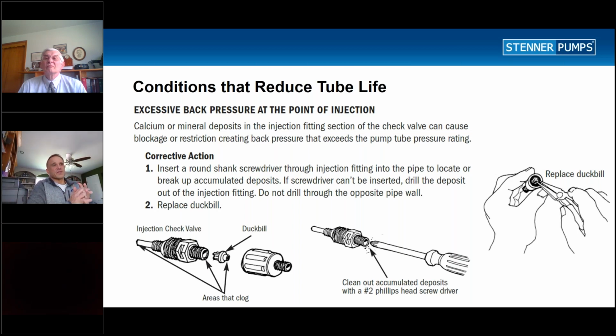Now, as far as reducing the tube life, every time that I change a tube, I'm going to change the duckbill. And we always feel it's best practice to take the end of your Phillips head screwdriver and stick it through the injector fitting just to get rid of any rust, calcium, or anything else that might collect at the bottom of the injector. I don't have a picture of it here, but what I also recommend doing is cutting the end of the injector fitting at a 45-degree angle. And when you place the injector fitting back into the T, you want to make sure that you're placing it in there so that the long side is facing the flow of water.